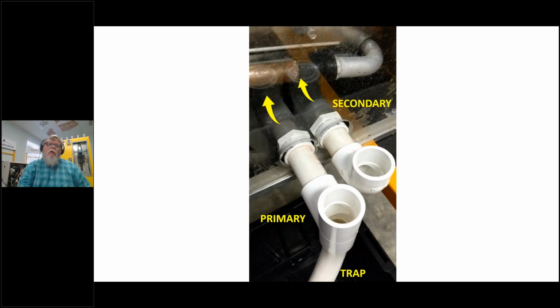See the arrows coming out of the drains. There's a primary and secondary drain. The guy on the left, I got the T opened at the top. The T being open on the top there is actually allowing air to be sucked in there. There's a trap under it, but the air gets sucked in. And on the right, they put this elbow in there. Maybe they turned it up, maybe they turn it down, whatever. Air's being sucked in there.